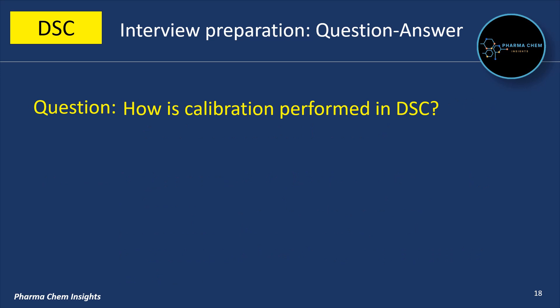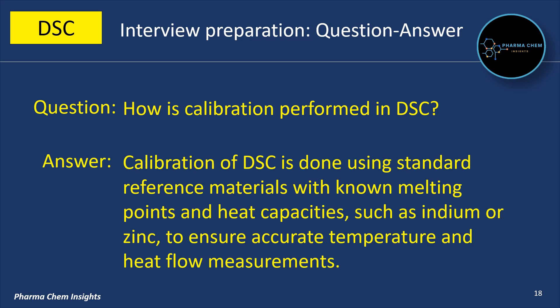Next question: How is calibration performed in DSC? Calibration of DSC is done using standard reference materials with known melting points and heat capacities, such as indium or zinc, to ensure accurate temperature and heat flow measurements.